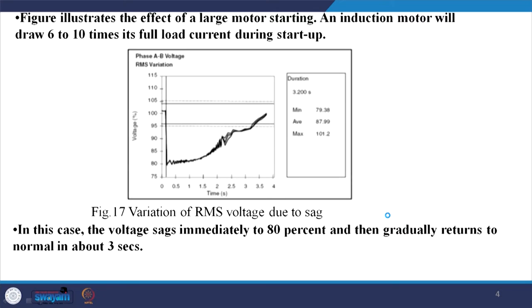Similarly, the next figure illustrates the effect of large motor starting. An induction motor will draw 6 to 7 times its full load current during startup, causing the voltage to fall. At the moment the motor is started, there is a fall in voltage from 100 percent to 80 percent, and it gradually returns to normal value after about 3 seconds. This is a case where voltage sag may occur.